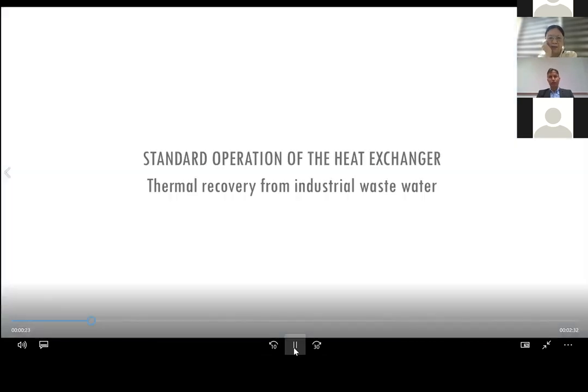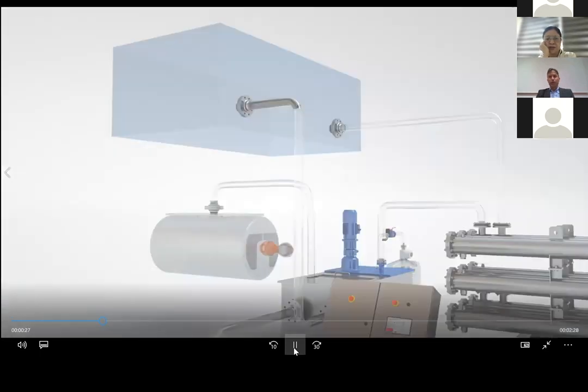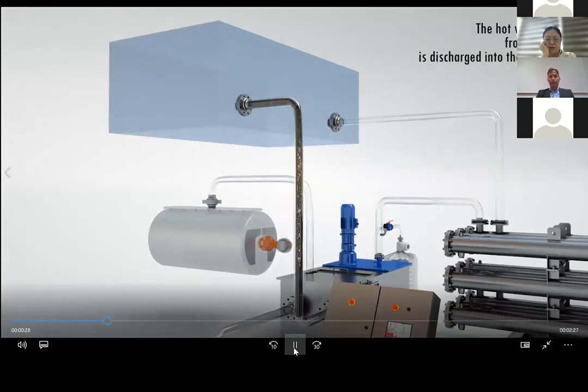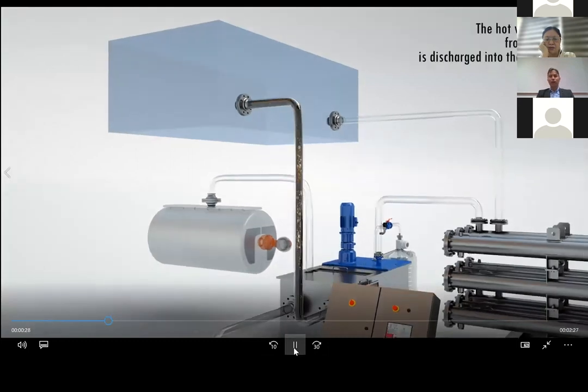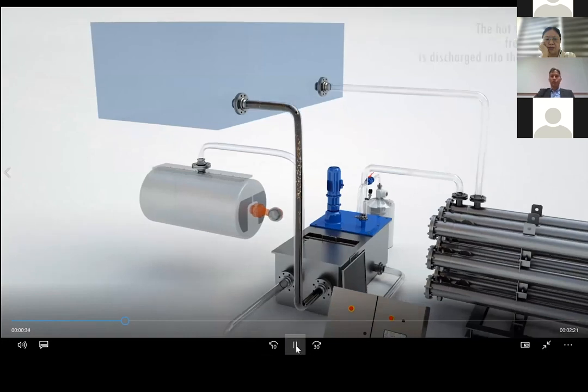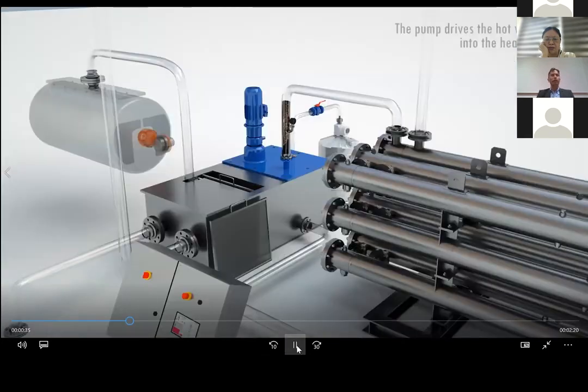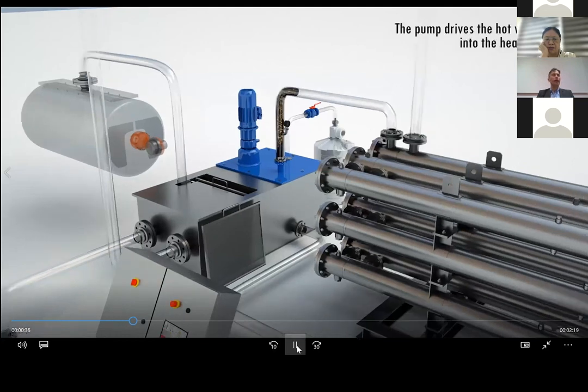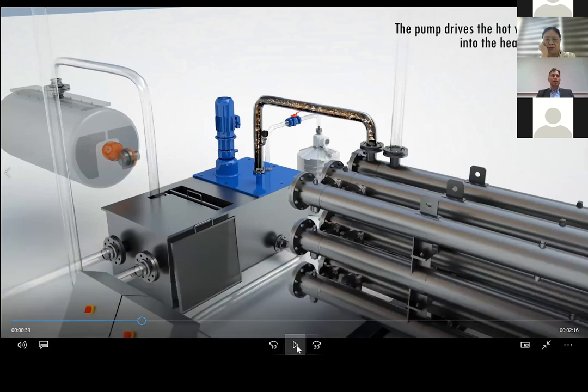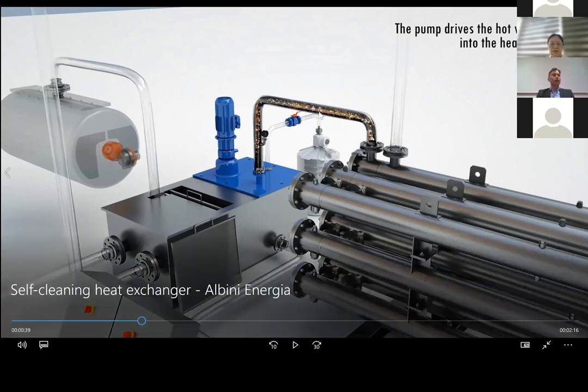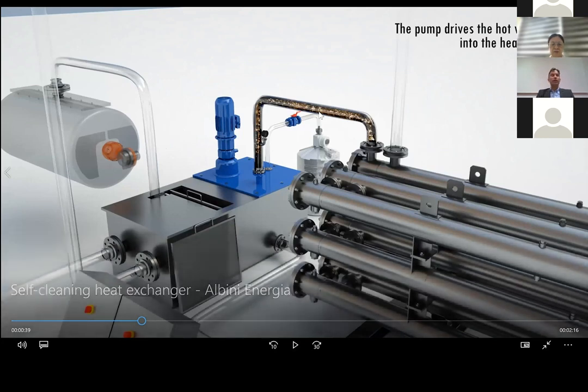That's the standard operation of the heat exchanger, so it shows how the system works. The wastewater goes into the tank and is pumped through the heat exchanger on the pipe side. In this case, we don't need a filter, because the pipe can handle suspended solid without any problem. In case of a plate heat exchanger, in this position after the pump, we normally insert a drum filter in order to remove all the suspended solid.